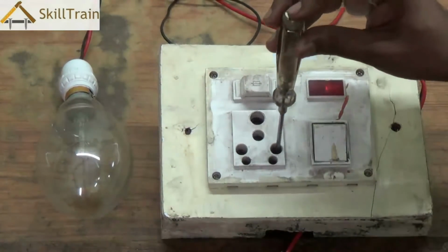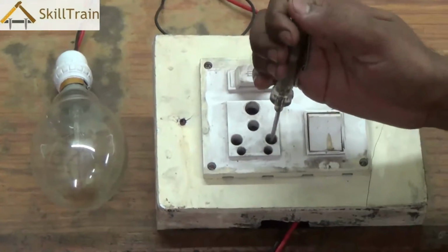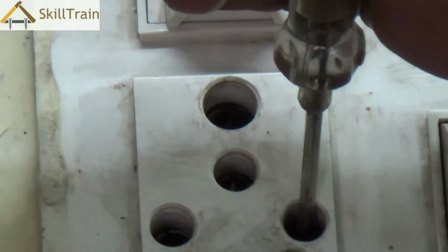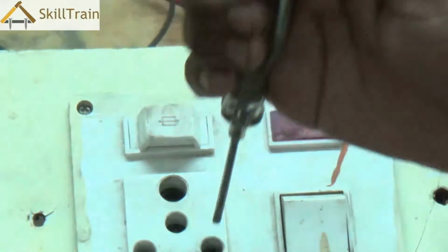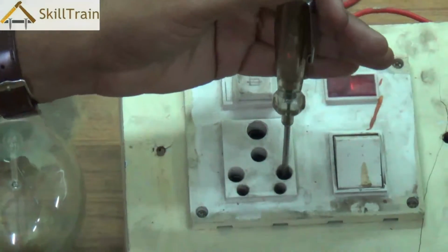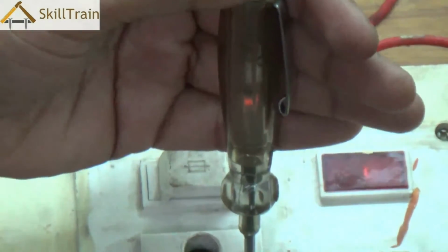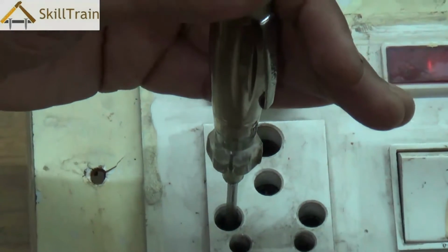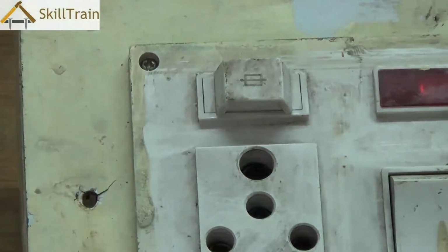In order to find out which is the phase, we place the tester in one of the plug holes to see if the tester is showing a light. As you can see, there is a light glowing here, which basically means that this is where the phase is connected into this plug point. When you place it in the other one, you will not be able to see a light there, which signifies that the other one is a neutral. So, this is a positive line or the phase line as we call it. You see that there is supply coming in here, and on the other hand, there is a neutral line which has no light showing up.